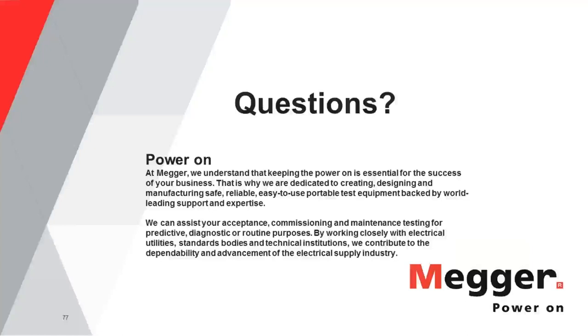What is the place of insulation resistance testing with MV cable? Second part of the question, there are other tests like AC, VLF, tan delta, etc. that seem to be the types of tests to use. Can test results actually tell whether a cable is bad or good?